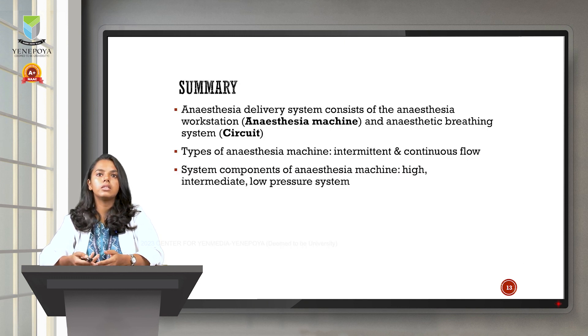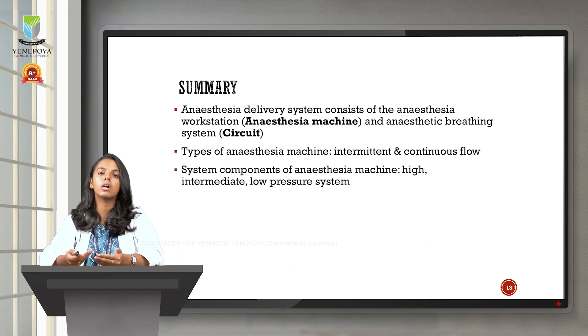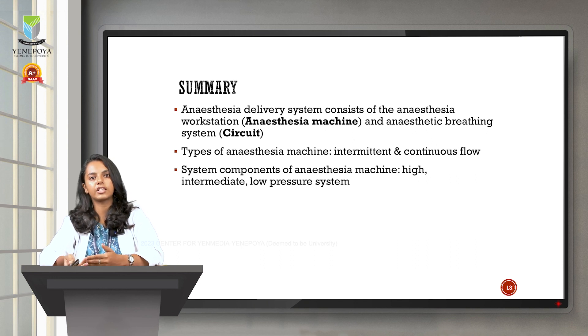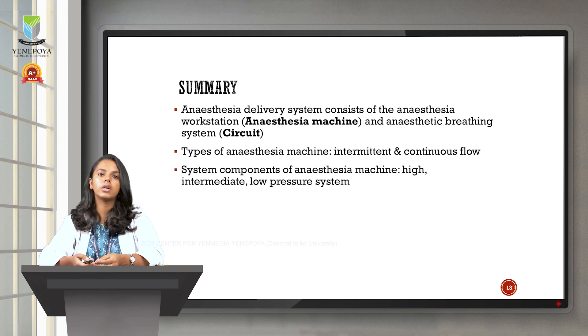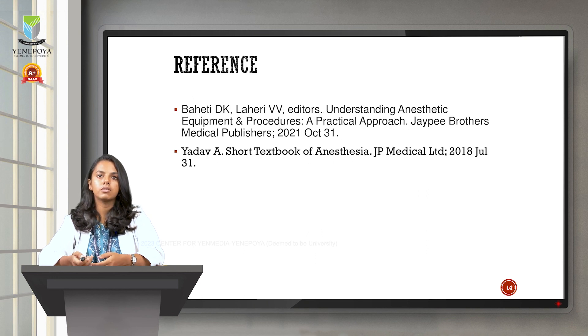In summary: the anesthesia delivery system consists of the anesthesia workstation and the anesthetic breathing circuit. There are two types of anesthesia machines — intermittent and continuous flow. In the intermittent machine, gas flow occurs only during inspiration; in the continuous flow machine, gas flow occurs during both inspiration and expiration. The components of the anesthesia machine are divided into three pressure systems: high pressure system, intermediate pressure system, and low pressure system.